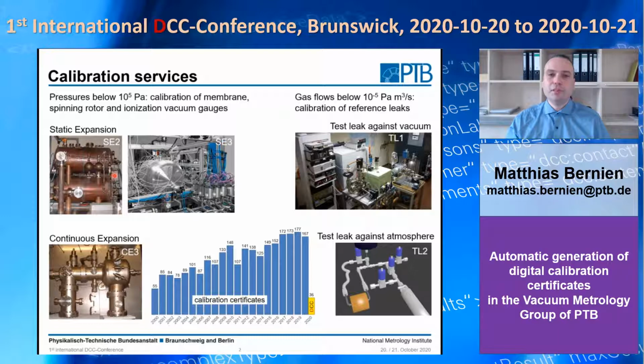At low pressures, outgassing dominates the uncertainty and a different method is used. This is a continuous expansion method, where a fixed gas flow is expanded into a volume that is pumped through a calibrated orifice. That's used for the calibration of ionization vacuum gauges. Reference leaks are calibrated by comparing their signal to the signal of a well-known gas flow from a flow meter by means of a quadrupole mass spectrometer, and similarly, reference leaks against atmosphere are calibrated.